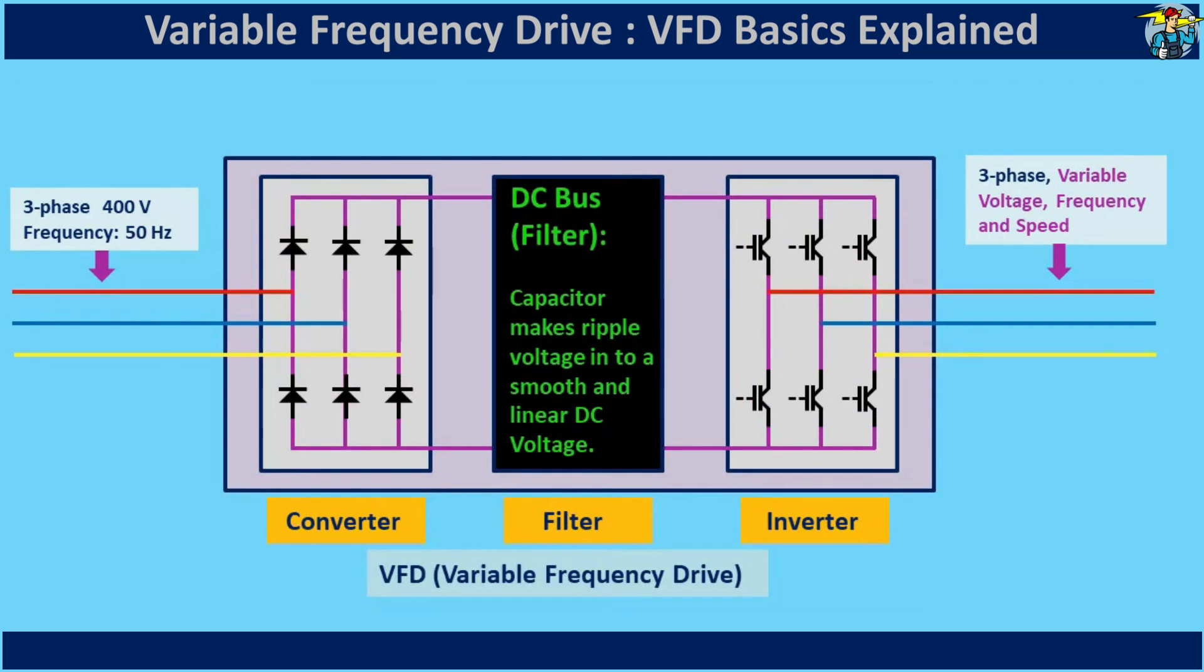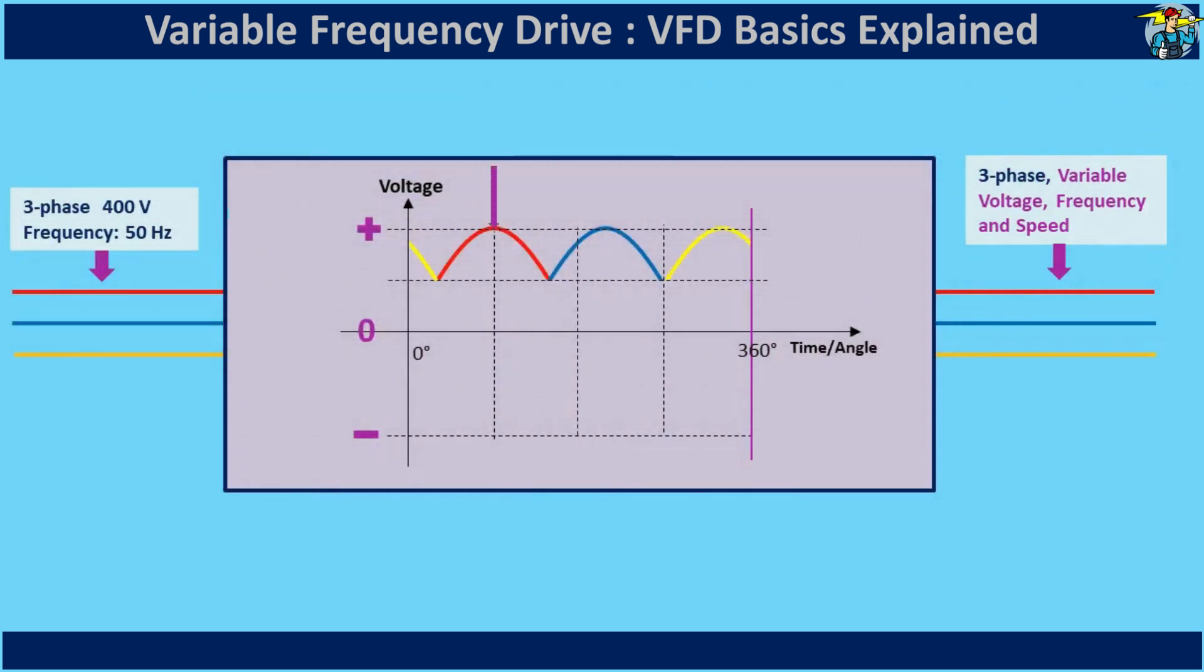DC bus is equipped with capacitors, and these capacitors convert the rough and rippled voltage into a smooth and linear DC voltage. When voltage is at its maximum, the capacitors are fully charged, and begin discharging to fill the DC gaps created during voltage dips.